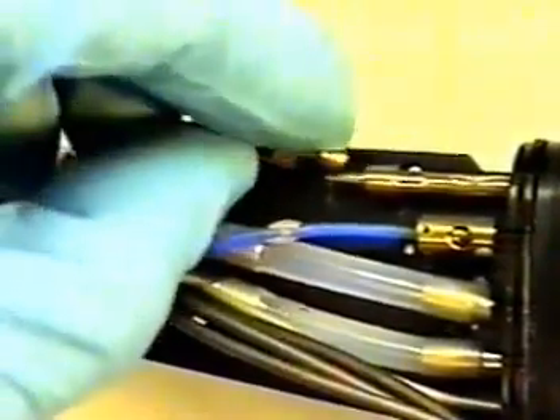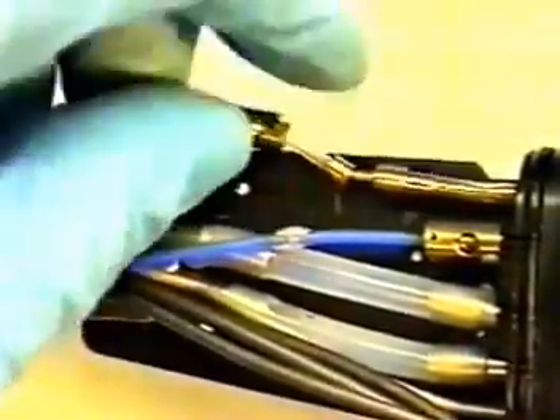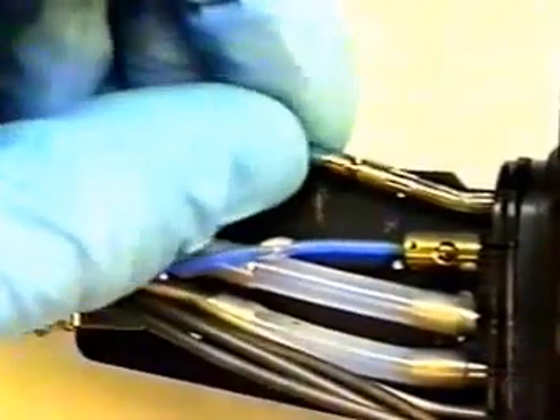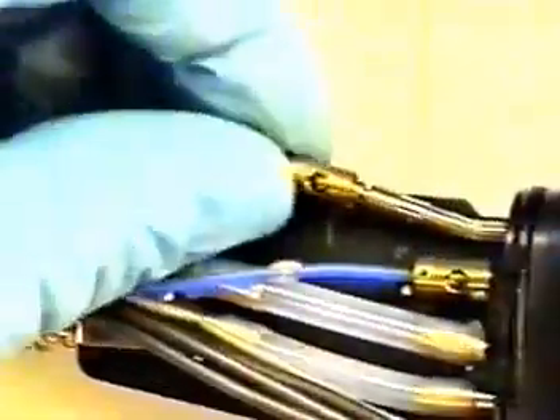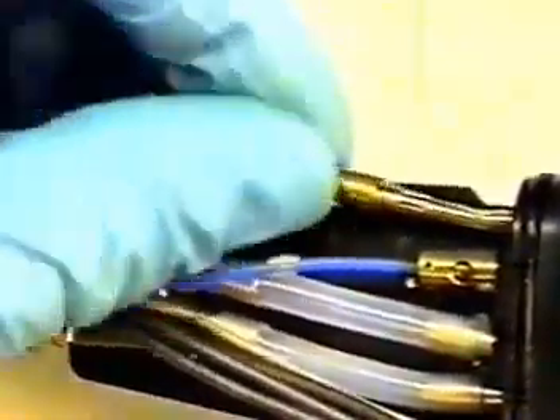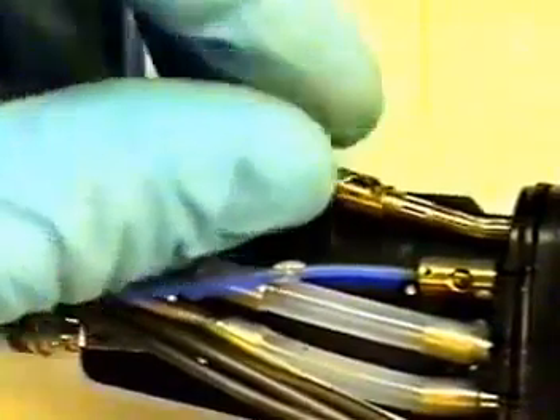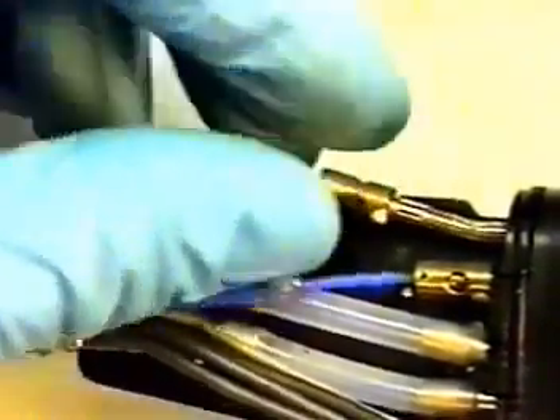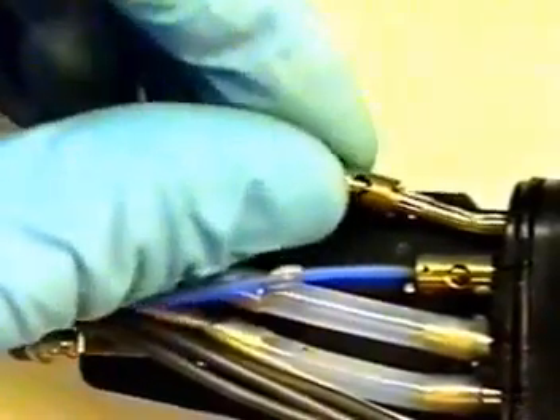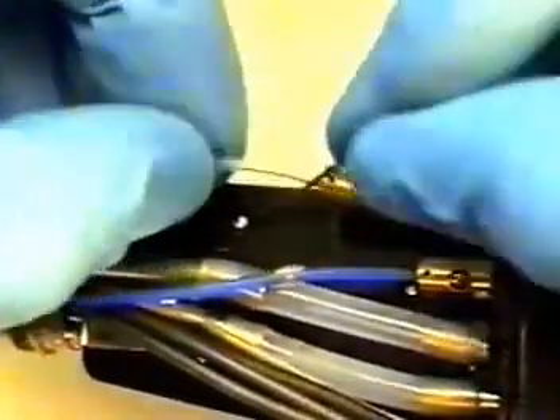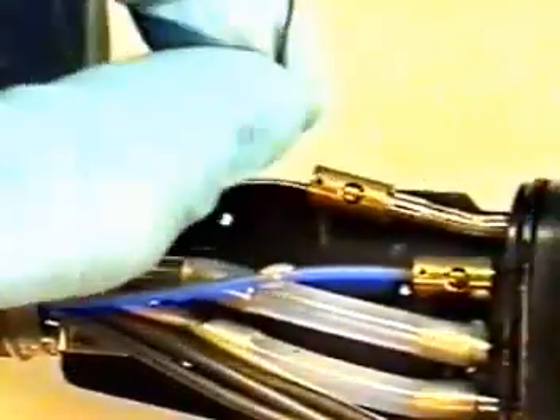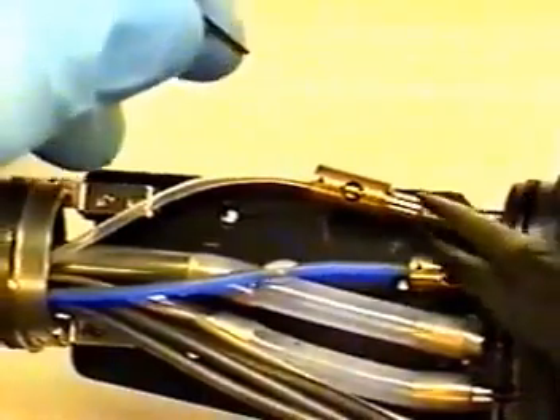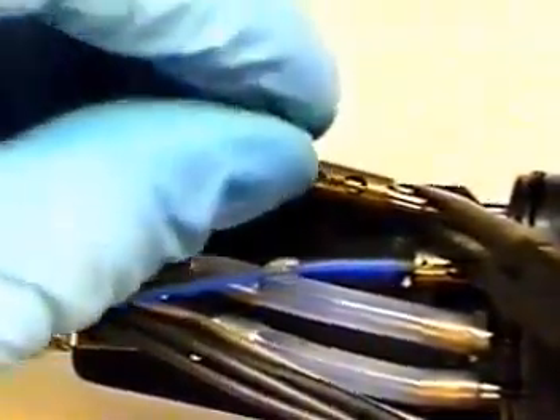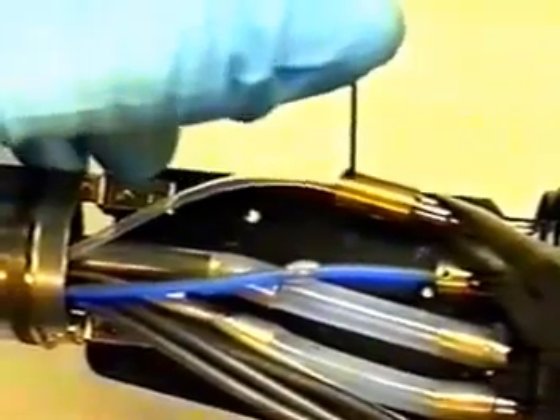Do the same for your clear channel, which will be at the top. Pushing ferrule down and tightening ferrule onto top air water assembly. Again, be sure that channel does not twist. Tighten with a small drill bit and hold small needle nose pliers to tighten completely.